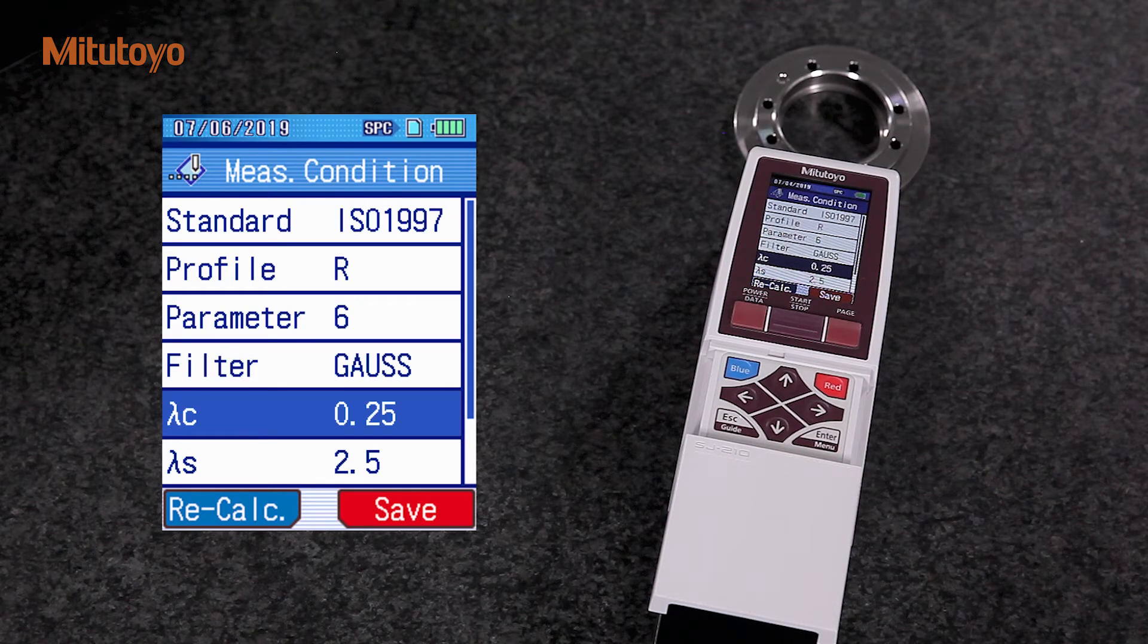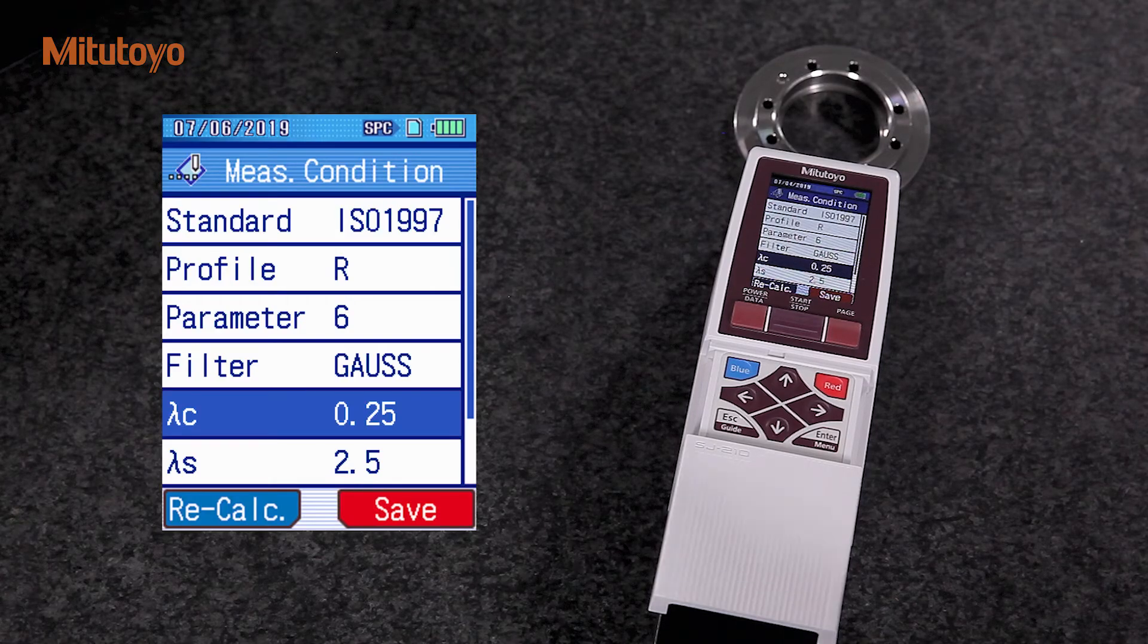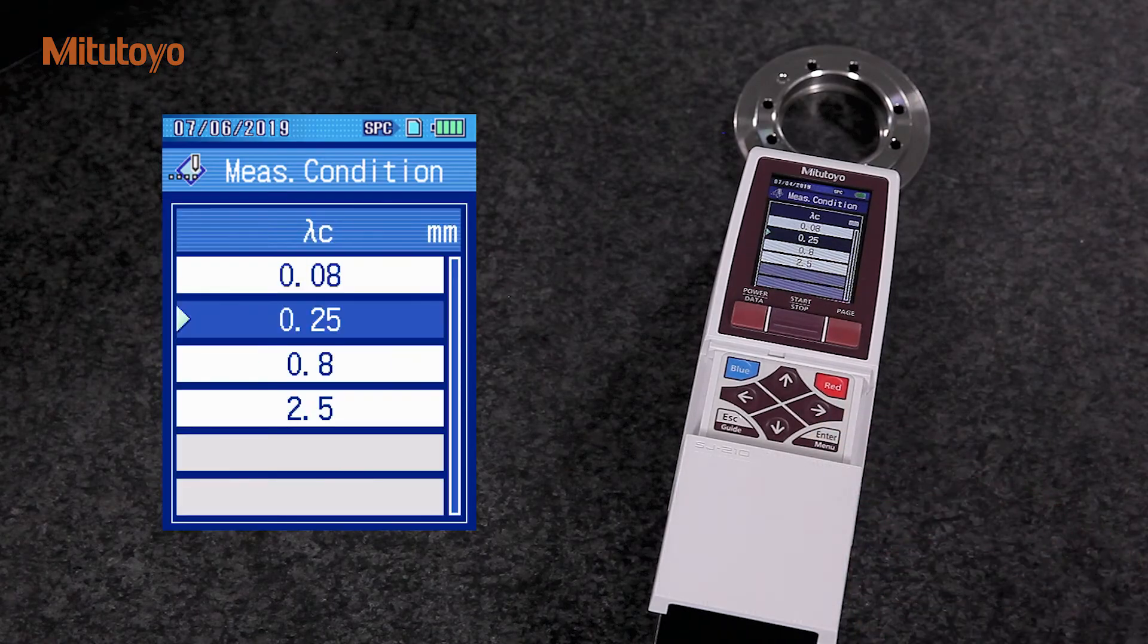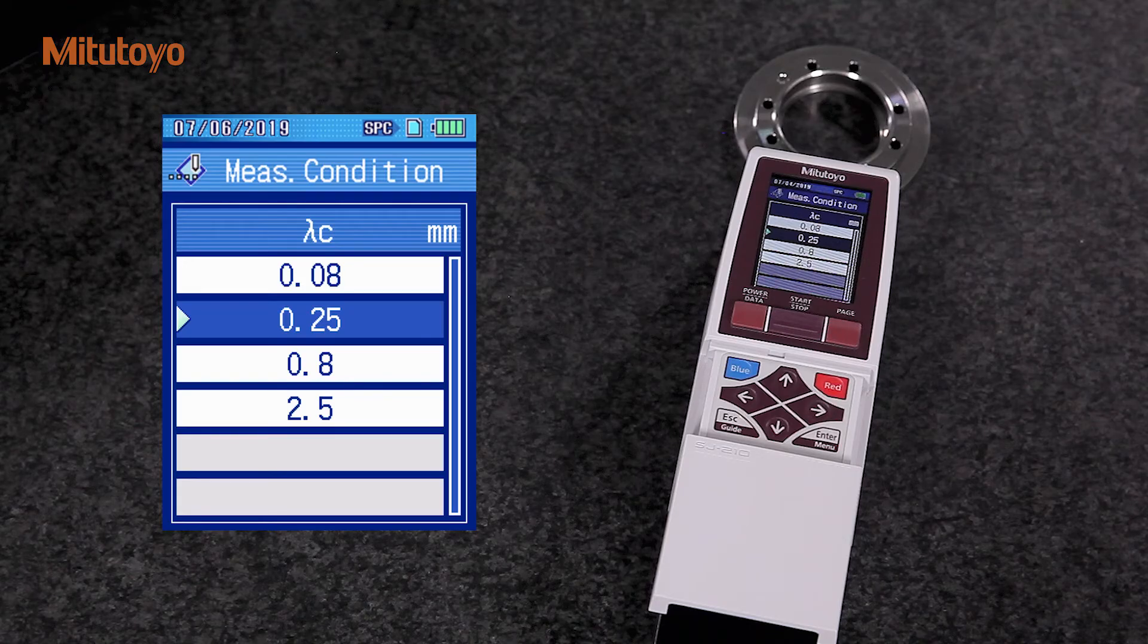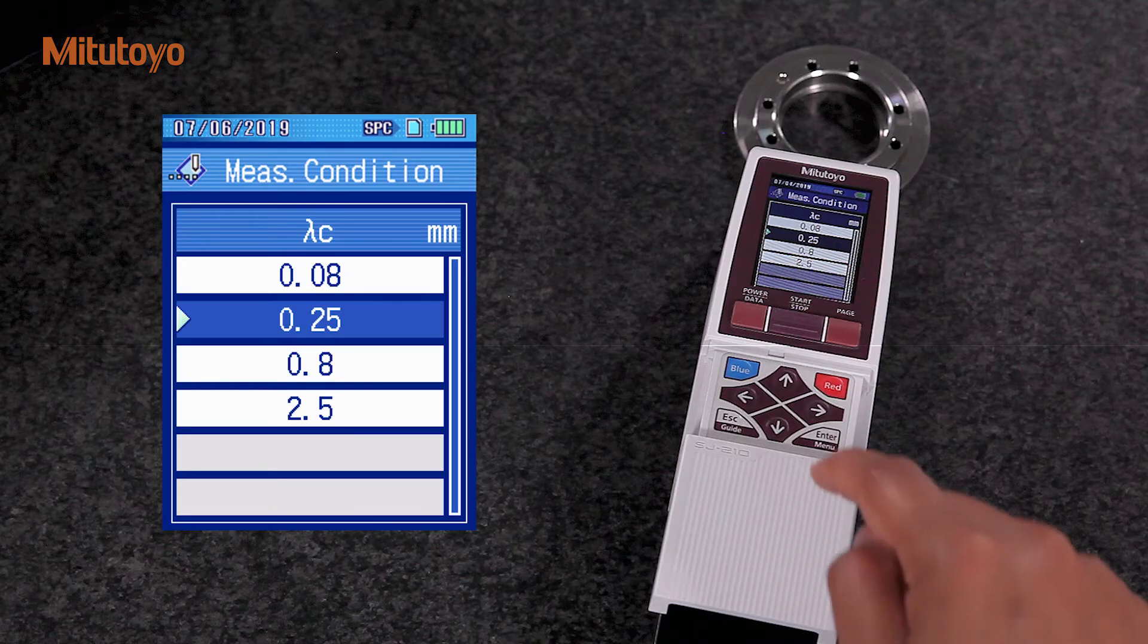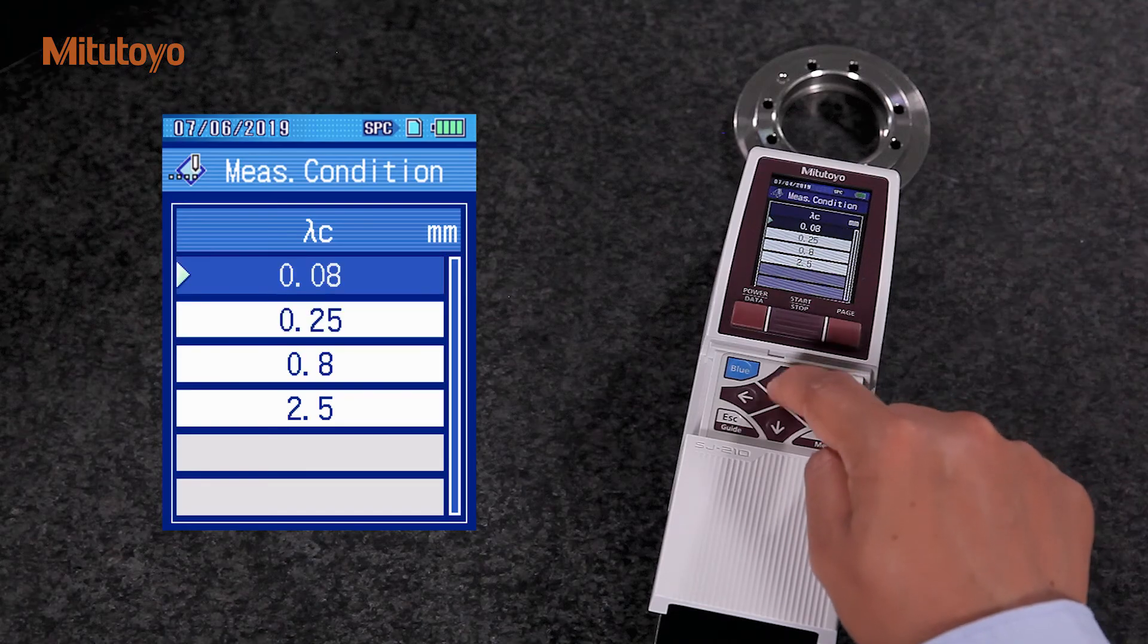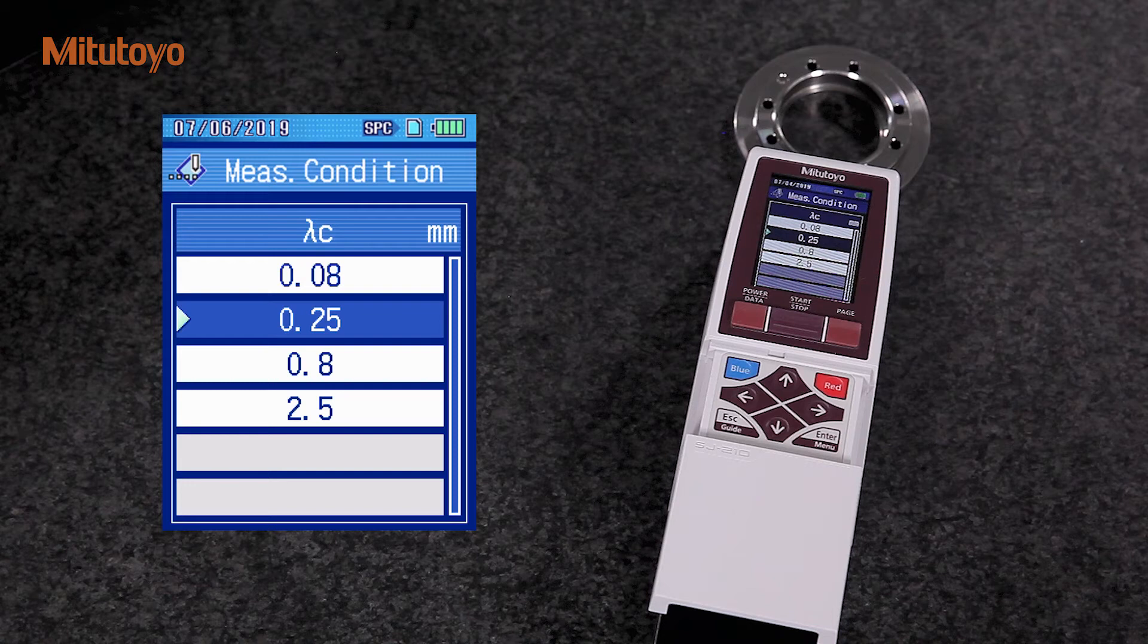Lambda C is the filter setting. This is one of the most important settings for roughness measurements. The selection of filter we apply depends upon the tolerance mentioned in the technical drawing. ISO 4288 provides us with the guideline for selecting the required filter. In this case, I will use 0.25.